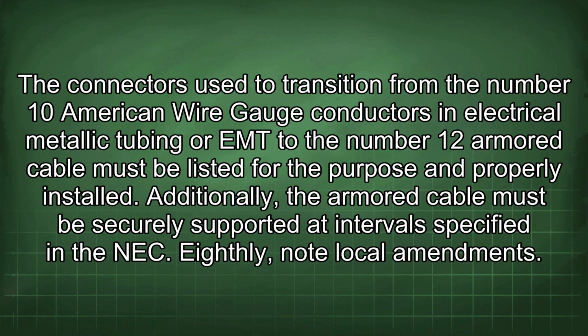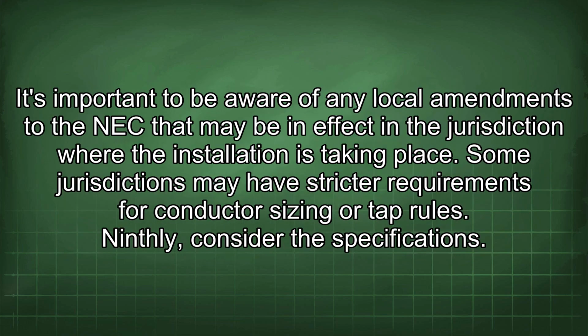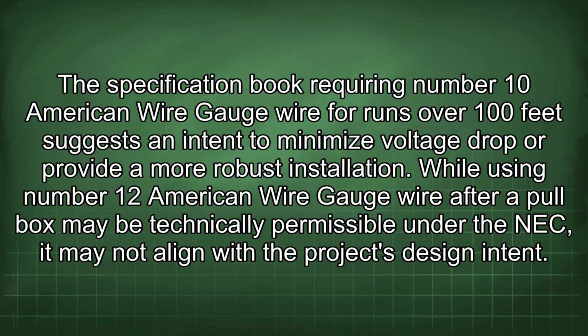Eighthly, note local amendments. It's important to be aware of any local amendments to the NEC that may be in effect in the jurisdiction where the installation is taking place. Some jurisdictions may have stricter requirements for conductor sizing or tap rules. Ninthly, consider the specifications. The specification book requiring number 10 American wire gauge wire for runs over 100 feet suggests an intent to minimize voltage drop or provide a more robust installation. While using number 12 American wire gauge wire after a pull box may be technically permissible under the NEC, it may not align with the project's design intent.